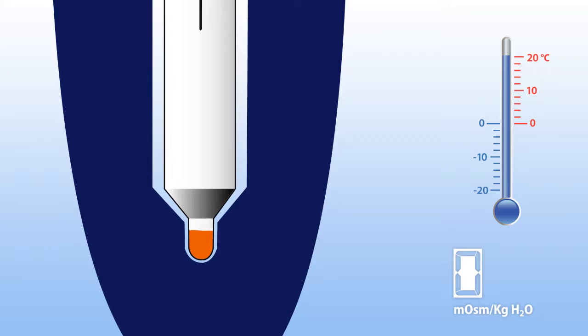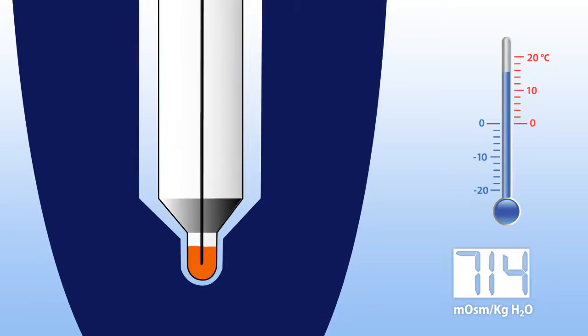Let's take a closer look at what happens inside the osmometer when a freezing point measurement is made. Once a sample is introduced in the cooling chamber, it is rapidly supercooled to a predetermined temperature below the expected sample freezing point.